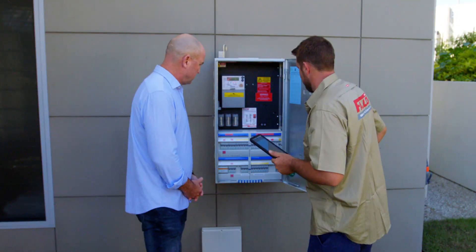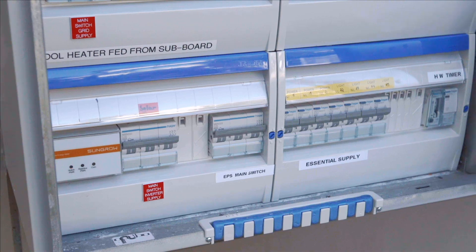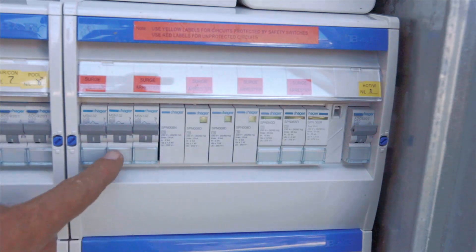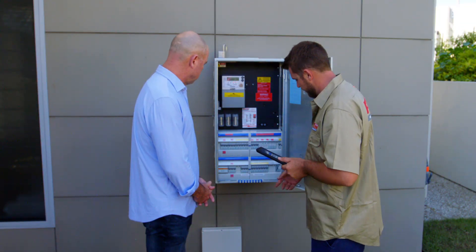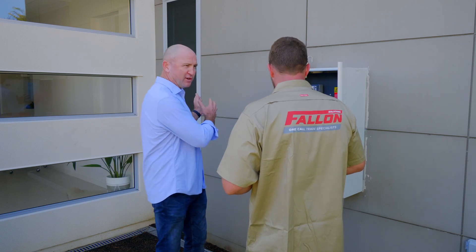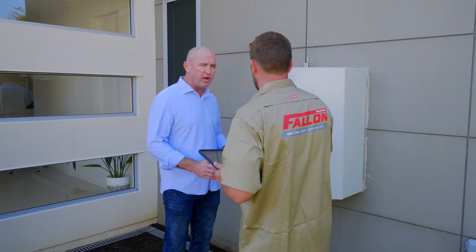Straight away we can tell this one's been reasonably upgraded. Everything's nicely labelled, nice and clear, so you know what's what. You've got the right protection equipment. You've also got the extra surge protection here, which is perfect for your inverter in case you get hit by lightning or something like that. The main switch has also been upgraded as well. So this setup is what it should be like if you're going to protect the expensive solar system — this is the ideal setup. Good to hear. So where do we go from here?